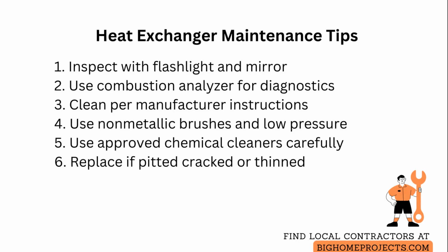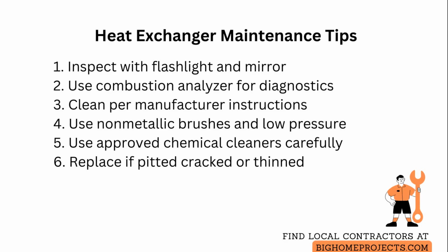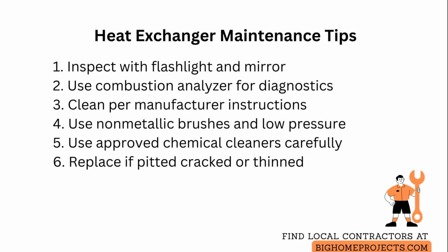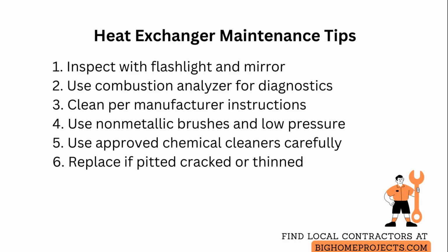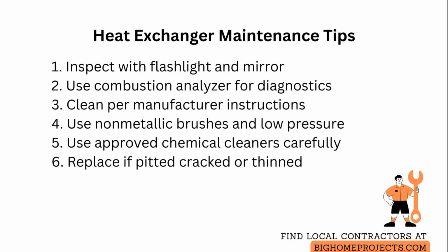When buildup of soot, ash, scale, or debris reduces the effective surface area or blocks passageways, heat cannot transfer efficiently and hot spots form on the exchanger walls. High local temperatures cause safety sensors or limit switches to open, shutting the system down to prevent cracks, warping, or ignition of nearby materials.